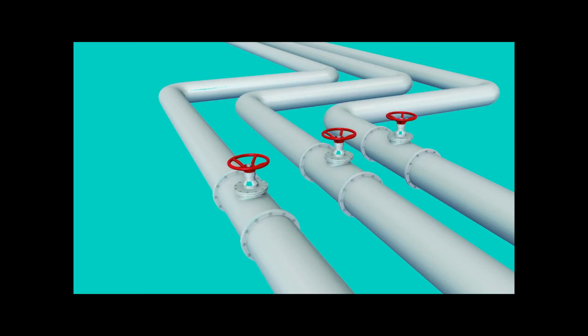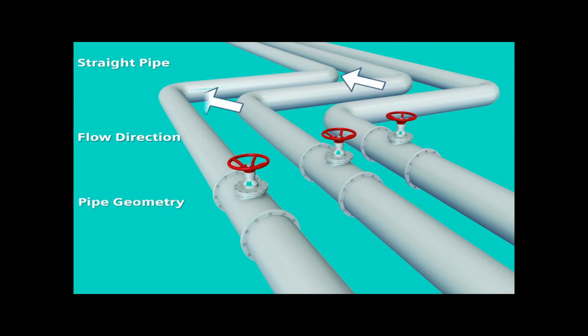So what should you consider when selecting a location to install your sensors? There's a few things to note. First, how much straight pipe do you have? You'll also want to note the flow direction, since the flow direction will determine where you will locate your sensors relative to the straight run. You'll also want to look at the piping geometry to determine what piping anomalies are occurring upstream of the straight pipe run. And lastly, the orientation. Is the pipe vertical or horizontal?